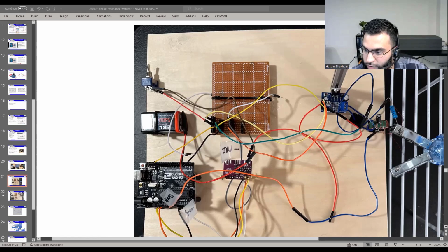Could you also set your current measurement reference on the battery side rather than the transformer side? That is a great question, and that is actually very true. That would work, measuring how much current is drawn from the battery, basically how much current it takes to drive this.